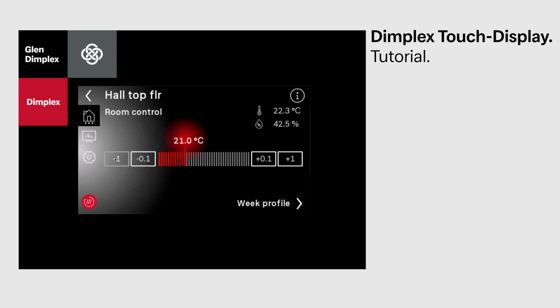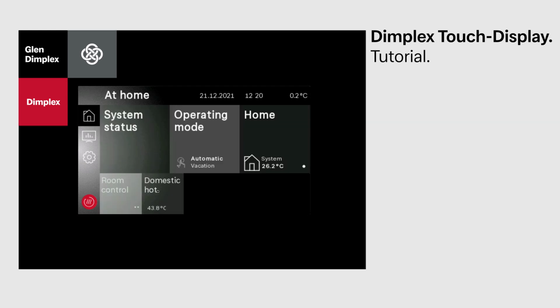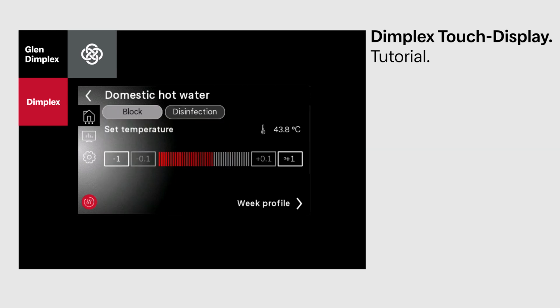Hot water menu. The factory setting for the hot water temperature is 50 degrees Celsius. If the individual hot water requirement is higher, the target temperature can be increased, which leads to higher operating costs. For reasons of hygiene, we recommend that you do not set the temperature below 50 degrees Celsius. More information on thermal disinfection and circulation can be found in the associated manual for the specialist and should be activated in consultation with the specialist if necessary.